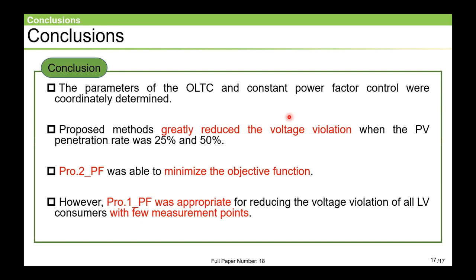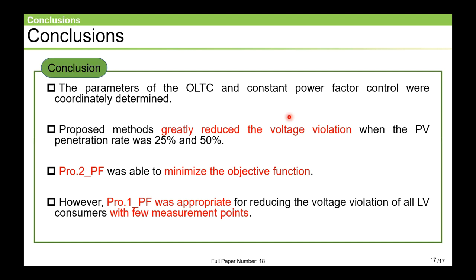Okay, let me finish with the conclusions. In this study, we proposed a method to cooperatively optimize OLTC and PV inverter parameters. The simulation results show that the proposed method can significantly reduce the voltage violation amounts, especially when the PV rate is 25% and 50%. In addition, in this study, PRO2_PF was able to minimize the objective function. However, when it was desired to reduce the voltage violation at all LV consumers with few measurement points, PRO1_PF was the most suitable. Thank you for listening. If you have any questions, I will be glad to answer them.